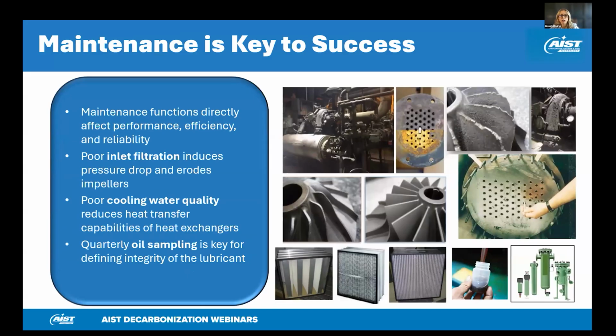Maintenance is a key factor to success, and that's in the performance, and that's the efficiency, and that's the reliability of the system. I would say with this slide, there's three main takeaways here. First and foremost, I'd like to focus on the inlet filtration. This is easy to schedule maintenance for the filters. Look at the delta P, the differential pressure across the filters.